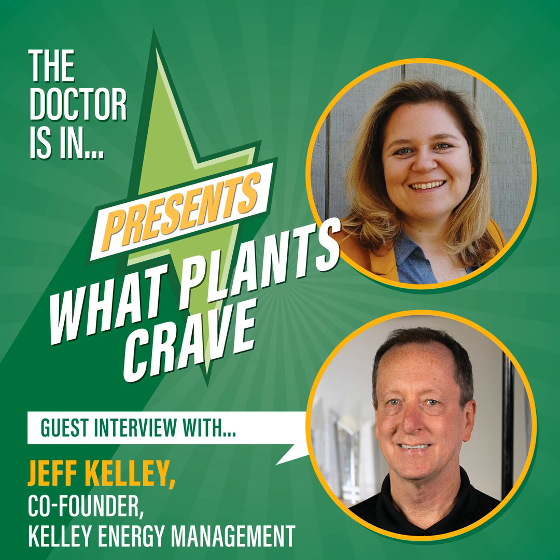And that's been a big issue that we've seen in a lot of the energy designs: they have a cliff. So their customer gets to week 8 and 9 and they want to do all these things to dry the room and super cool it. And the equipment just quits working. It's not designed to do that. It's designed for the average. So that's an interesting part of the calculation.